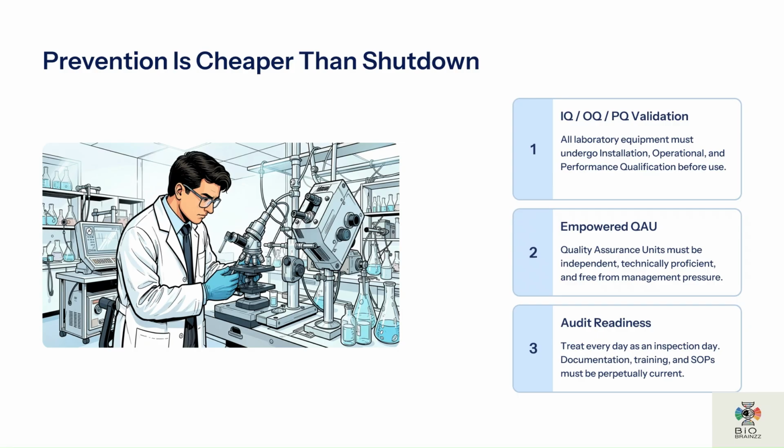Training records, SOPs, study records, and calibration records should always be updated. Remember, inspection readiness should be a daily habit, not a last-minute activity.